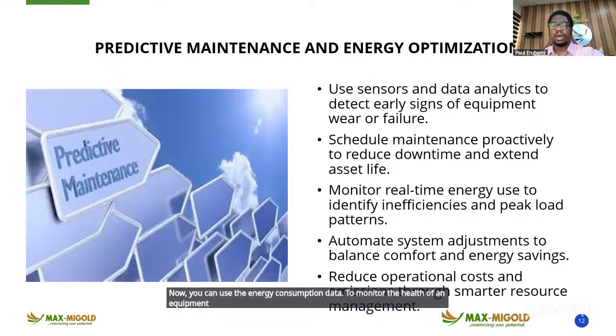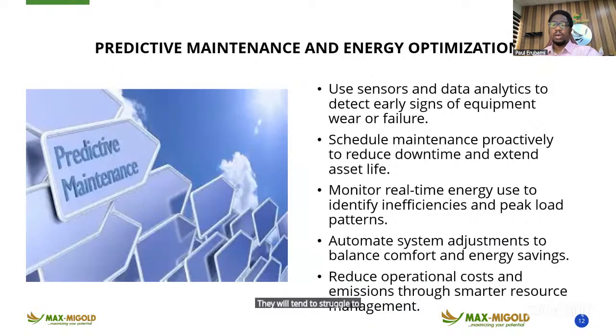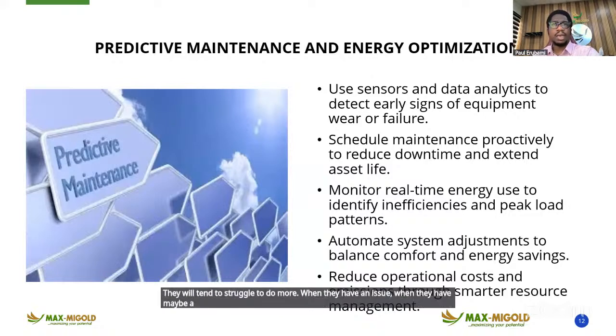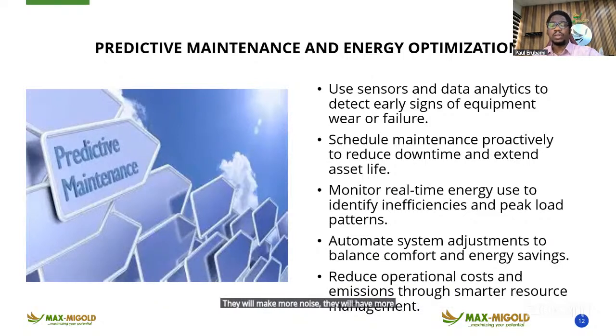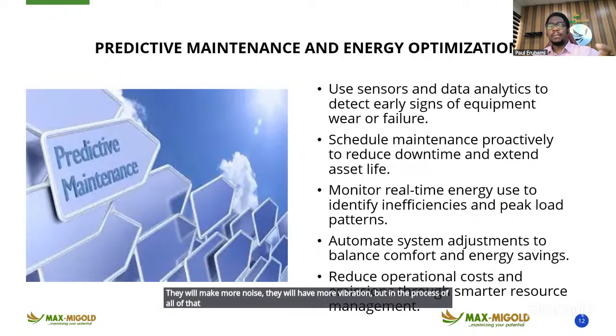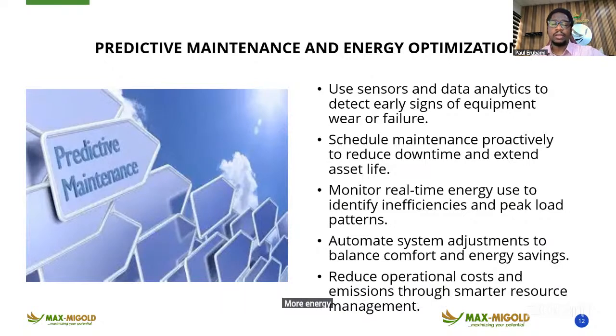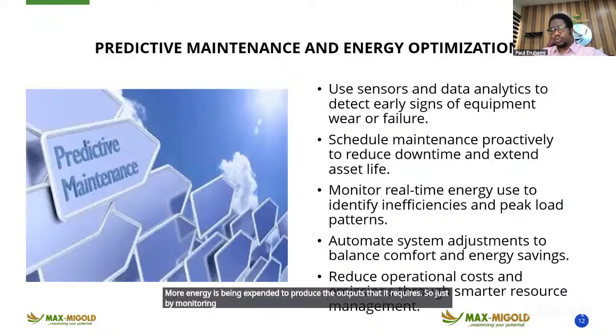Most equipment in your facilities will tend to struggle more when they have an issue, maybe a belt misalignment, maybe excessive vibrations from a certain pulley that is not in position or a bolt that is loose. They will make more noise, they will have more vibration, but in the process, more energy is being expended to produce the outputs required. So just by monitoring that energy use profile, you can tell something is wrong with the equipment.